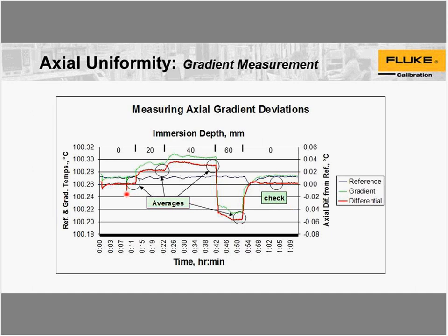You need to let those thermometers rest, dwell at the temperature for a sufficient period of time that you can get some stable data. So I've represented that by a circle. So we've got this portion of data which we know is stable, it's finished making a transition. We know that for each depth measurement.